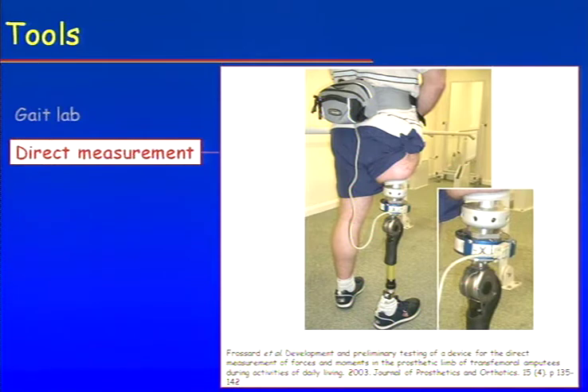Basically, what you see here is the process as we use it. The amputees are fitted with their usual prosthesis, so these are very ecological measurements. The major component is a little transducer placed between the knee and the abutment. The abutment is sticking out, and what you see is the device that protects the abutment against larger torque — so it's a protective device. In that configuration, the loads are transmitted directly from the knee to the abutment, giving us fairly realistic and intimate measurements of the load applied.